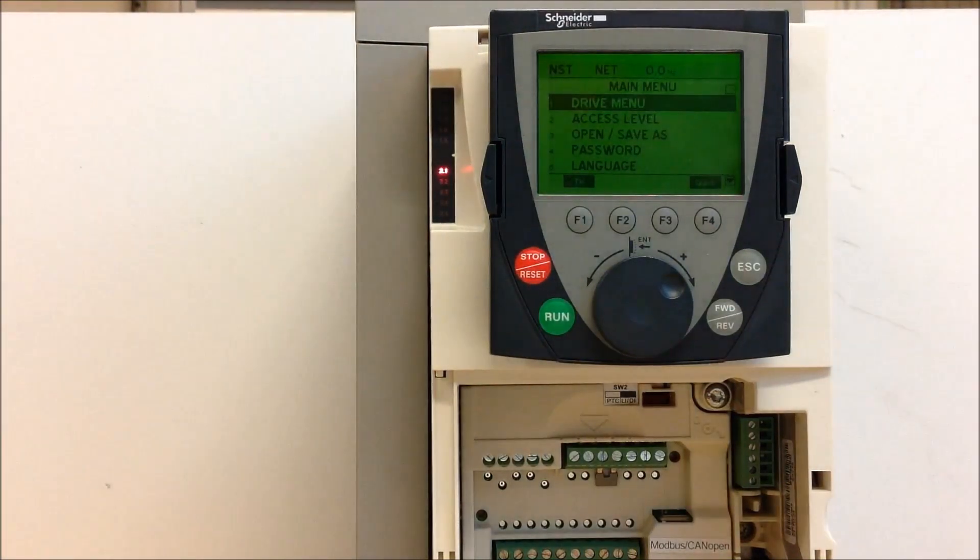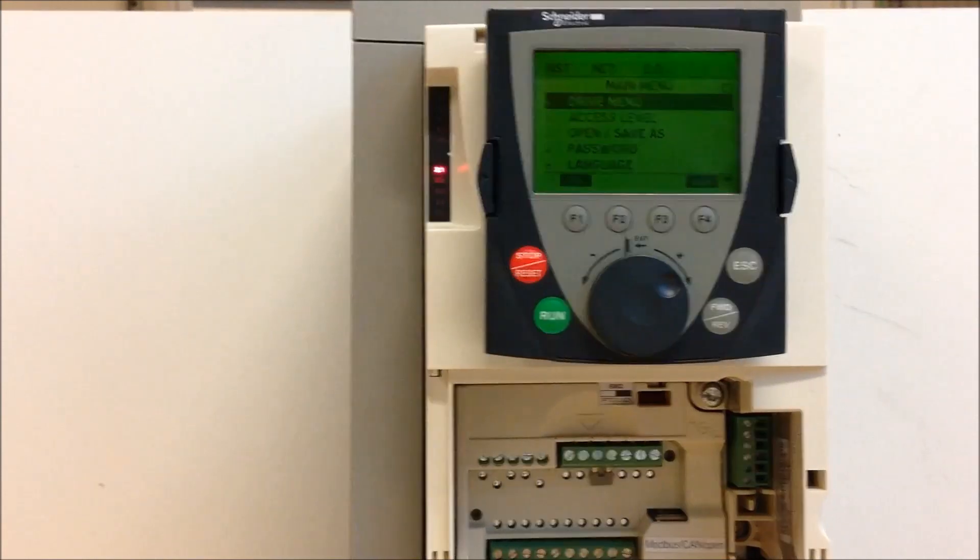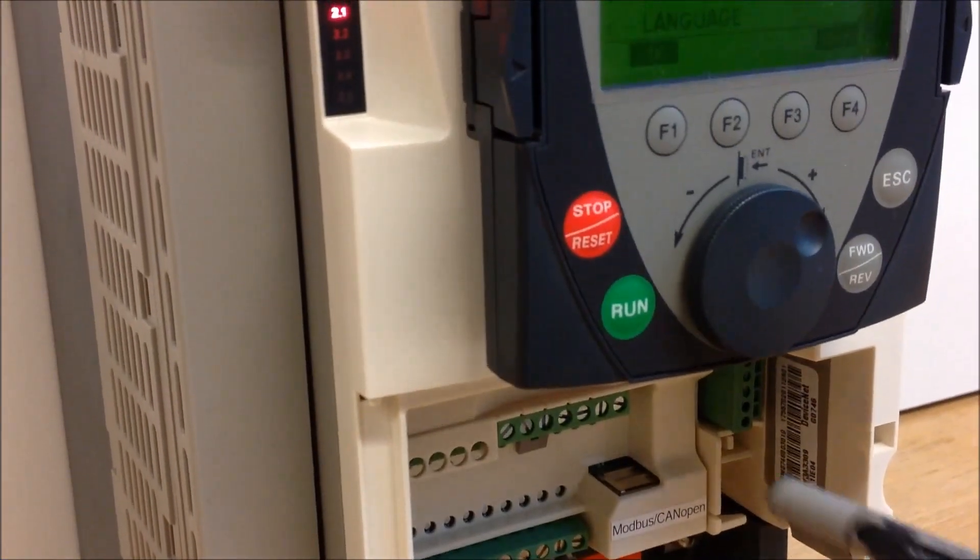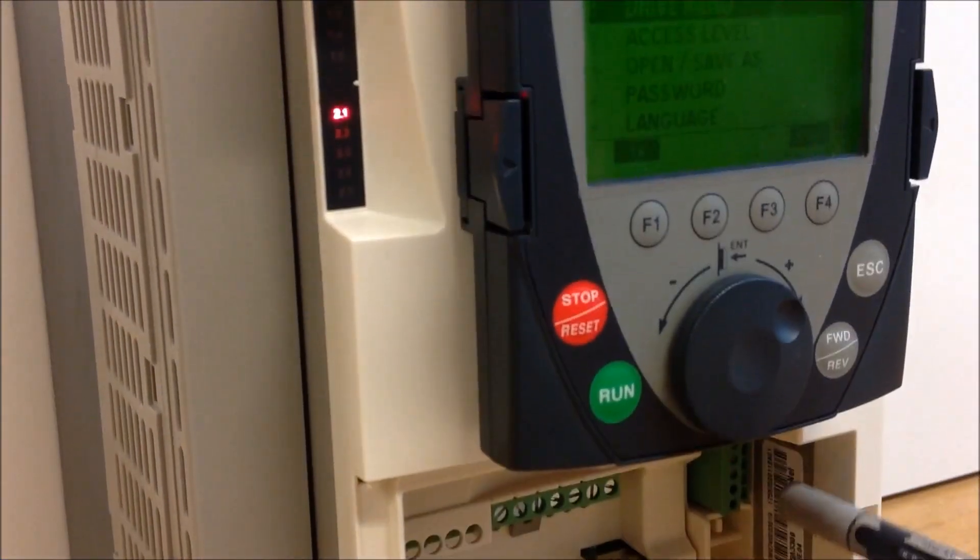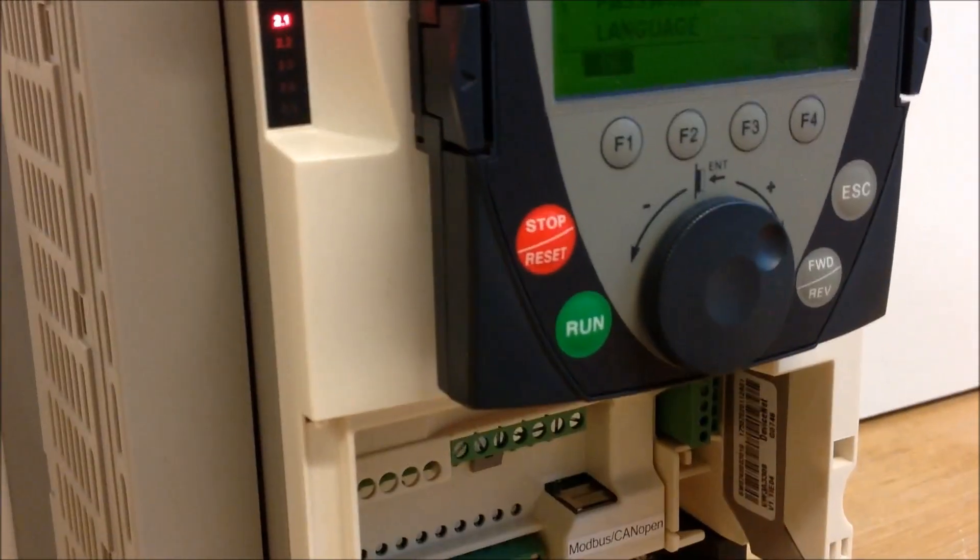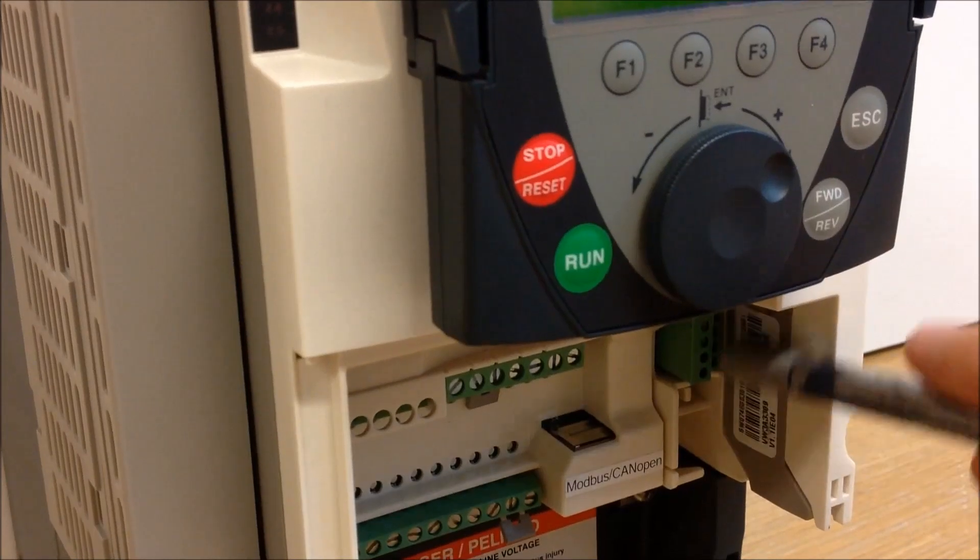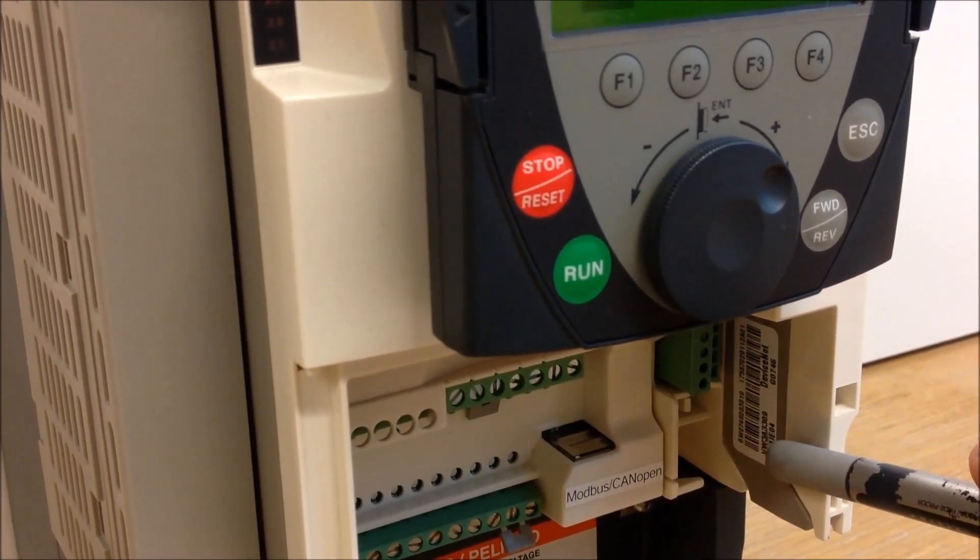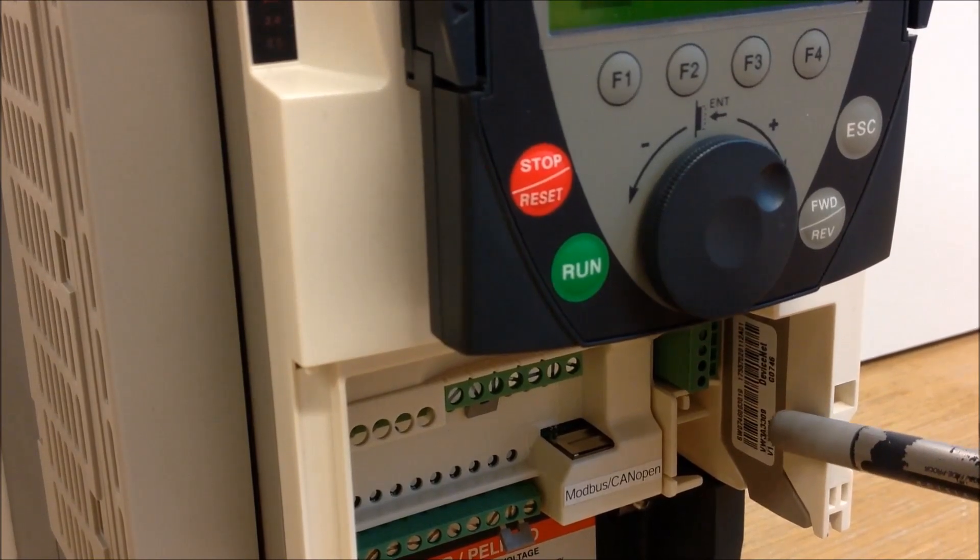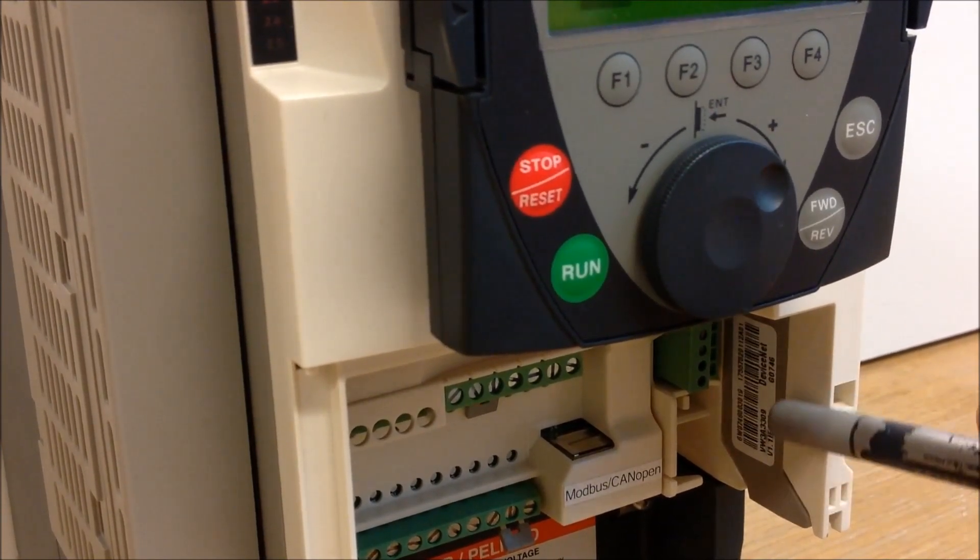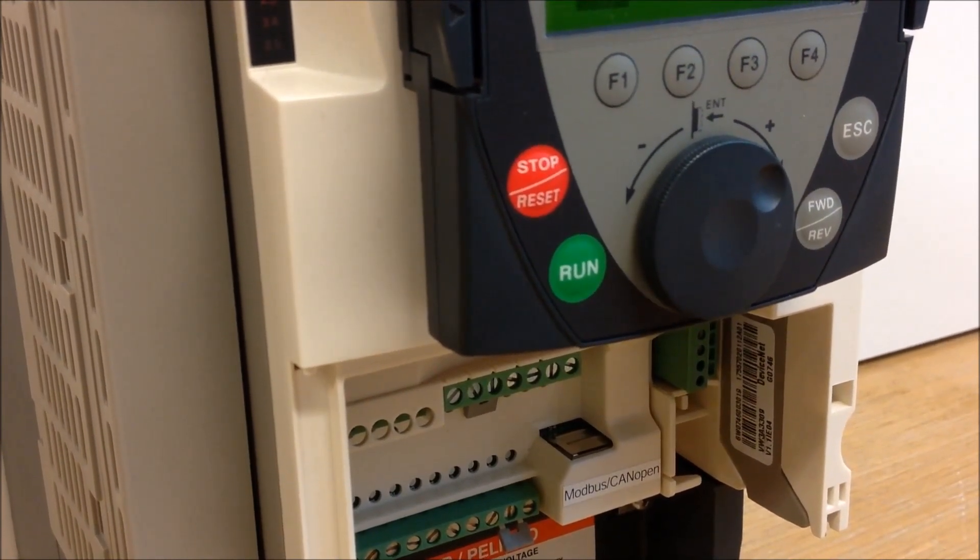There's a couple of ways of determining this. One way is to confirm and see what the barcode shows. As you can see, for example, the option cards are actually behind the actual cover of your drive. There will be some barcodes on each leg of your card that will tell you what it is, and there will even be a part number, such as this VW3A number, that will tell you what the actual option card is along with the part number.